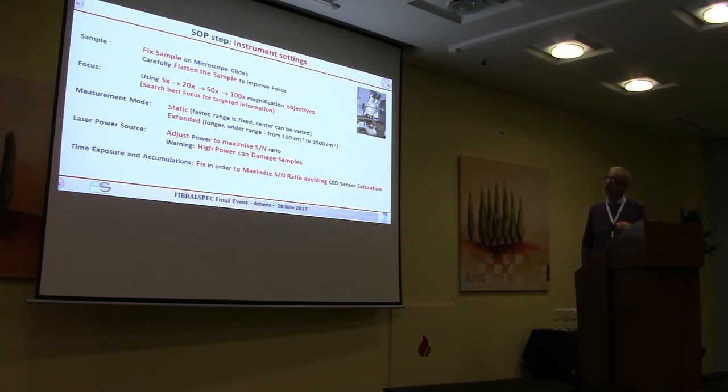You pick the measurement mode. There are two different measurement modes which are commonly used. You have to pick the laser power in order to maximize your signal-to-noise ratio, but you have to remember that high power can damage samples. So you have to be careful about not running your experiment with too high power. And then you have to fix the exposure time and accumulations in order to get the best signal-to-noise ratio again, but to avoid saturation.